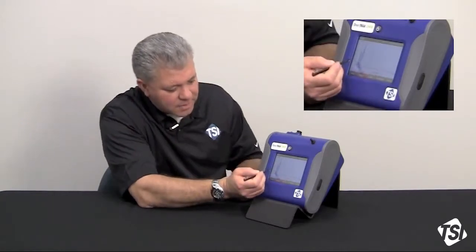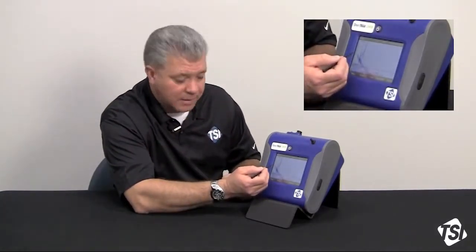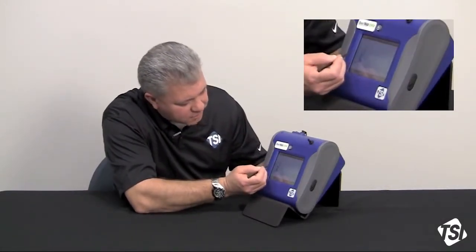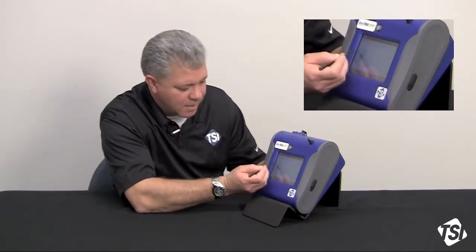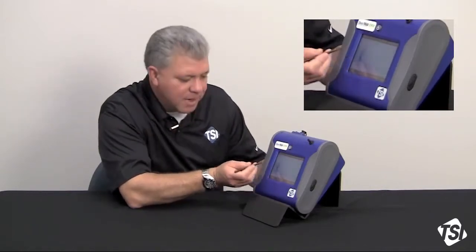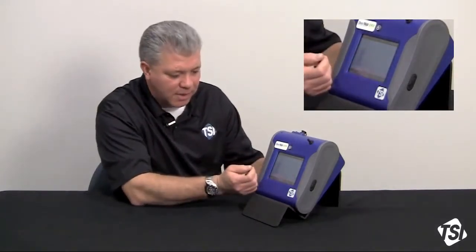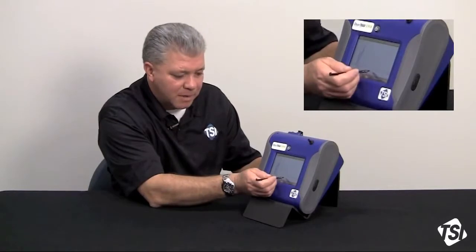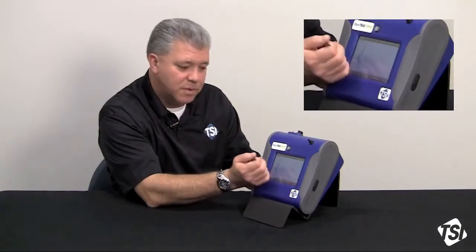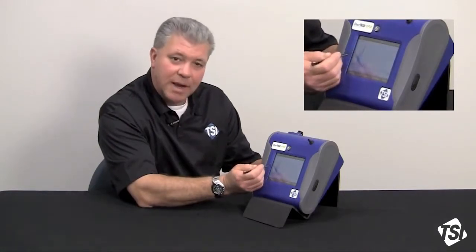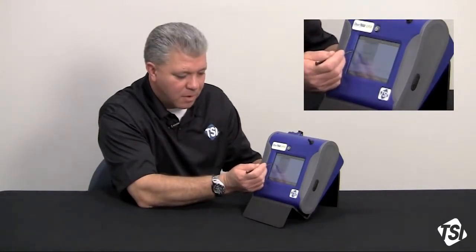Over in the y-axis, right now, we've got total being displayed. I can touch over here in the y-axis and change the size fraction. Now I have PM10. Now I've got respirable. I've got PM2.5 and PM1. You can actually see the screen changing. Down at the bottom over here under time, I can change my timing conventions from relative to actual and so on and so forth. It's just how you want to perceive and look at your data on the x-axis. But it is really a nice tool to be able to toggle over on the y-axis.